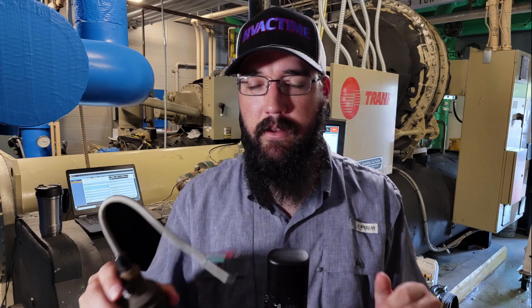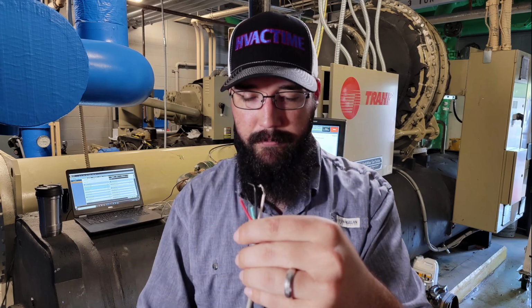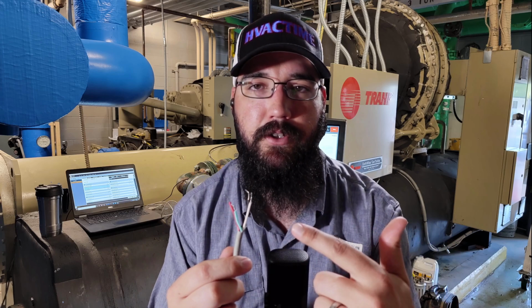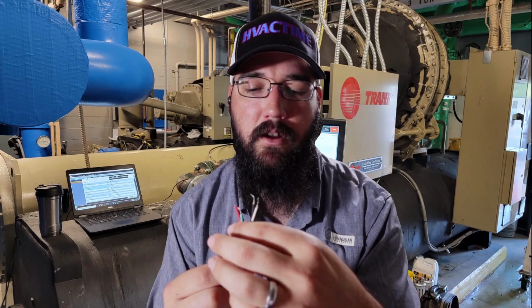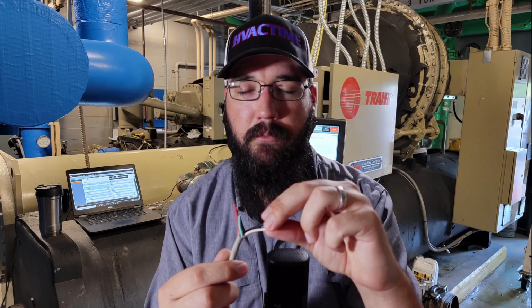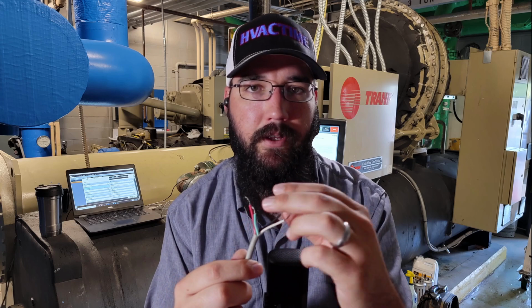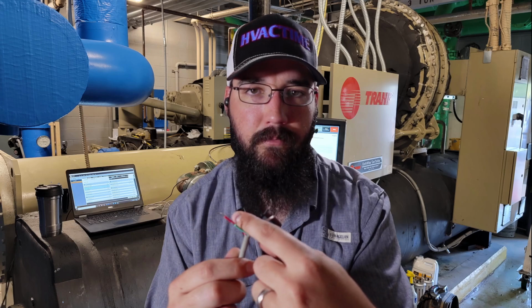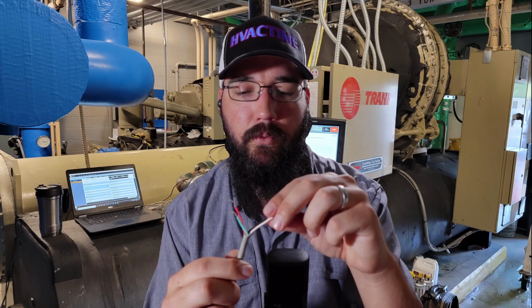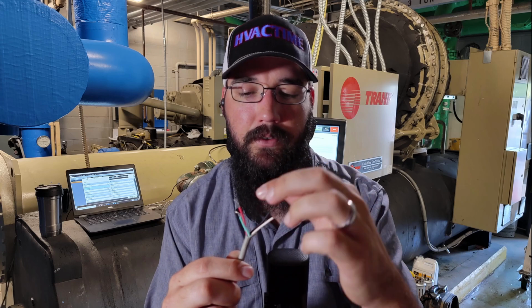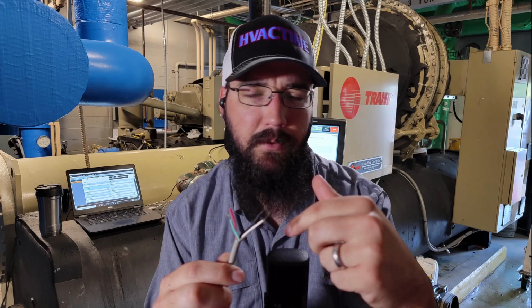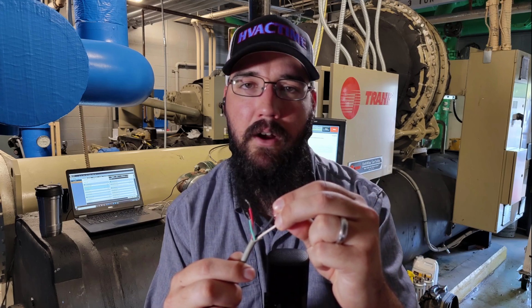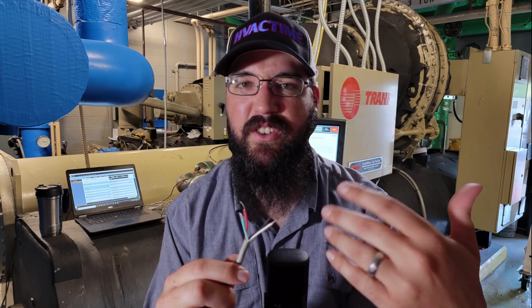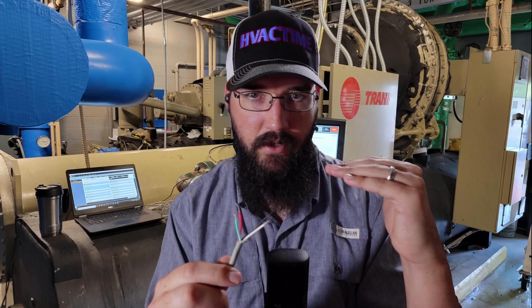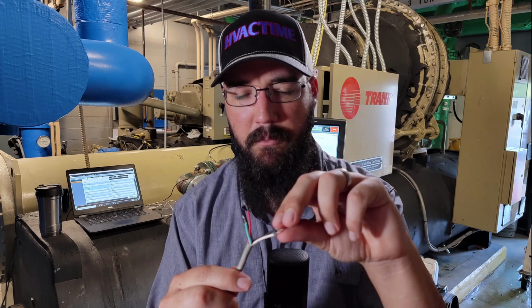is fairly simple for most of these. It is quite literally as simple as you get your leads. Whether this is pulling them off the terminal block, or whether you have a plug here, either way, for a 4-wire, 2 wires go together for each coil, for each stator. And so, reading resistance between these two, I will get resistance. Between these two, I will have resistance. So this particular valve is like a 50 ohm valve. This could fluctuate a little bit depending on the manufacturer and the size of the valve. So this changes. There's not just one standard for this. But just to kind of paint the picture.